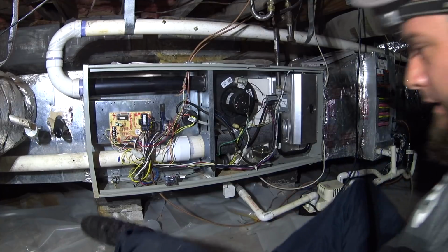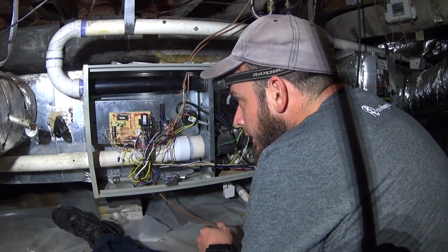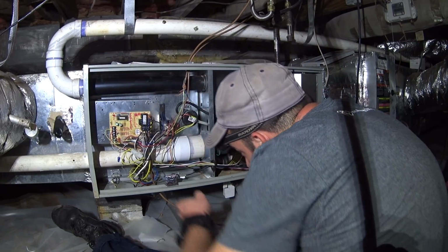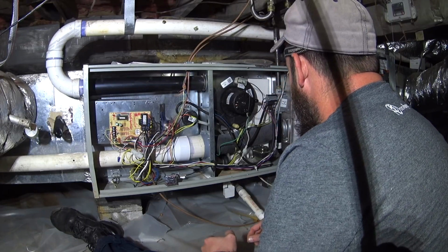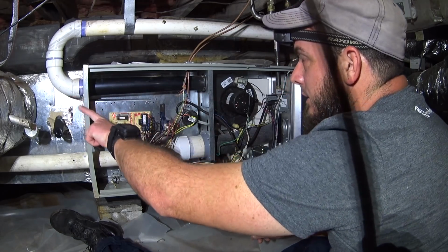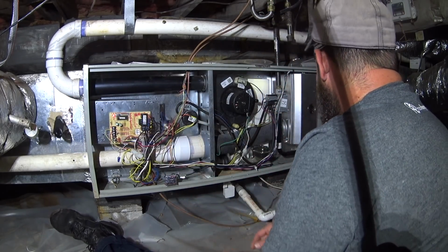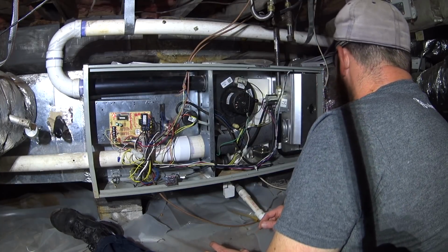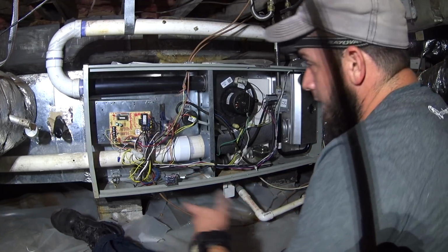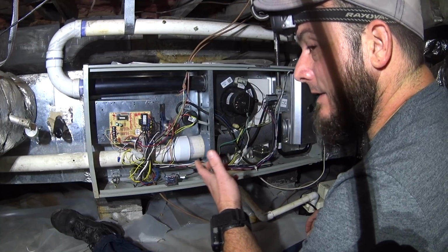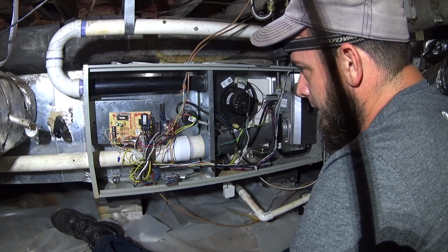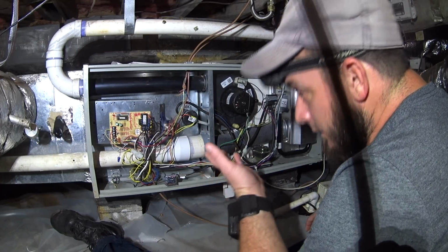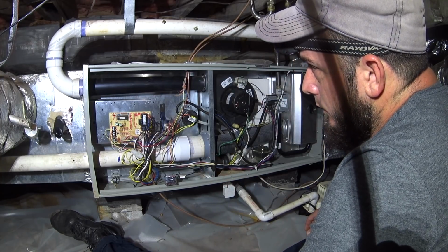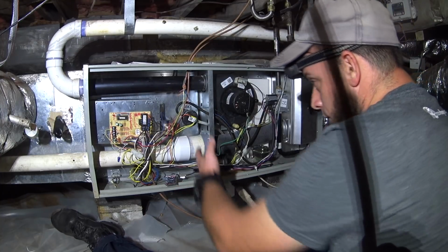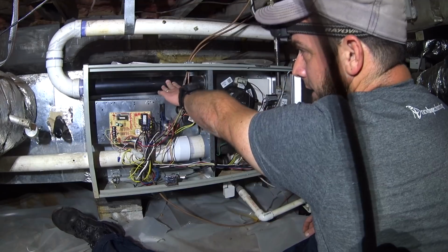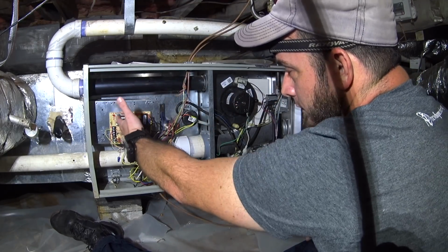Now, I do have a bit of an issue with how Trane does their blower cabinet on these downflows. Obviously, if you have to get your vent pipes out the top or the bottom of the unit, depending on which way you're oriented, it is nearly impossible to do anything different. But this is a blower capacitor, or a PSC blower motor, and as a PSC motor, there's a capacitor behind that wall. But to get to that capacitor, you would have to remove all of this piping, the black pipe, as well as the white pipe here, as well as the circuit board.